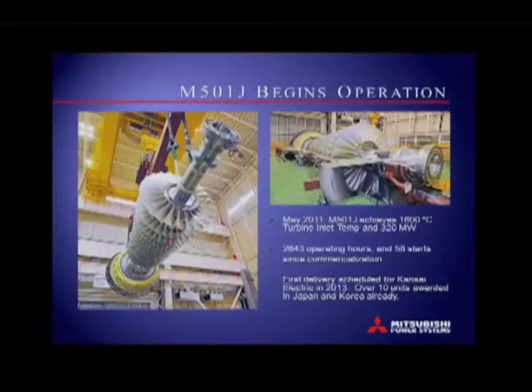This past February, we at Mitsubishi celebrated the successful commercialization of a 320-megawatt, 1600C firing temperature gas turbine at our factory in Takasago, Japan—our Mitsubishi 501J gas turbine. This unit, through nine months of demonstration, has shown thermal efficiency in excess of 61%, or 5,992 BTU per kilowatt hour on a heat rate basis.